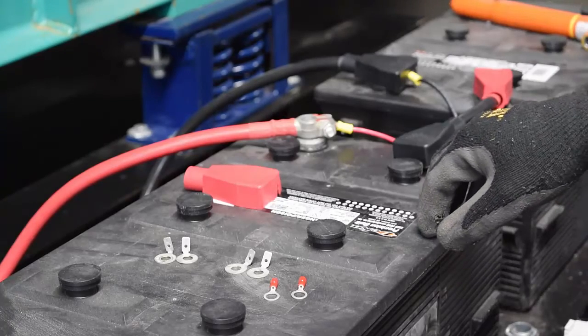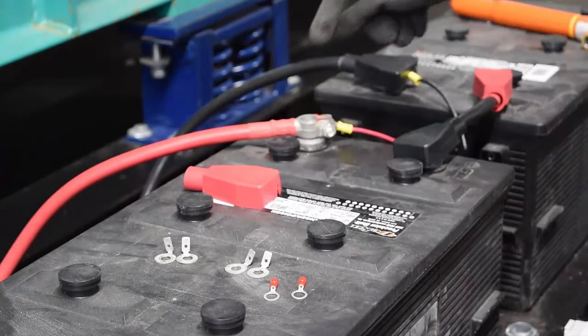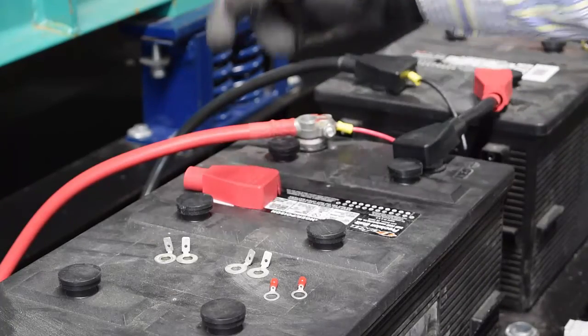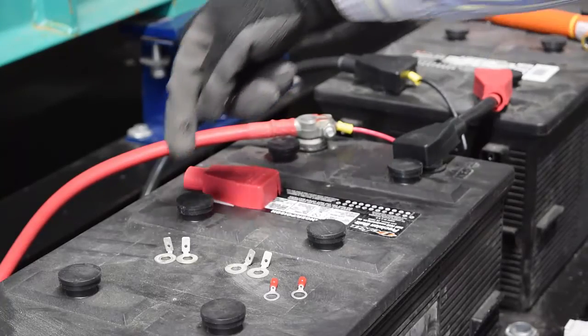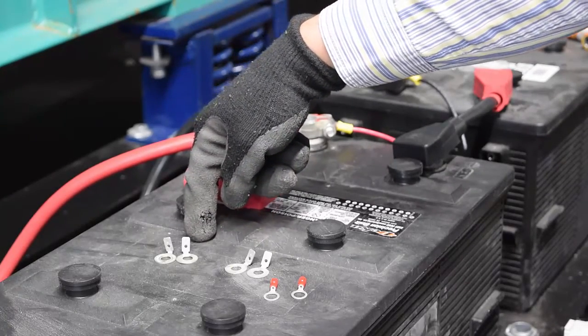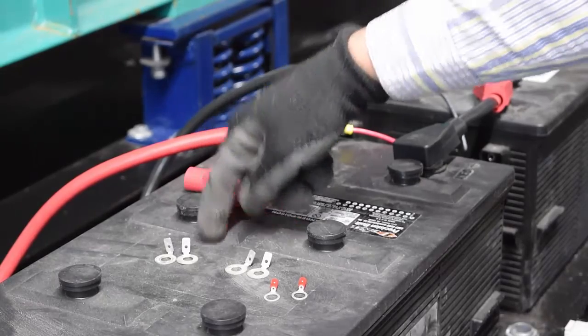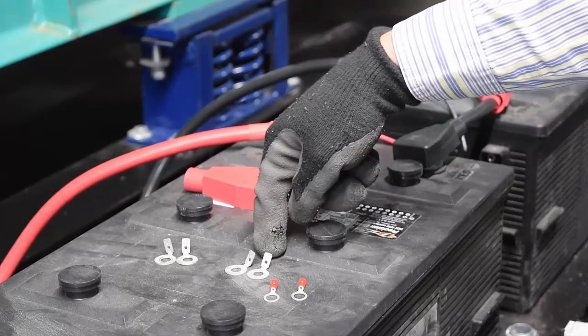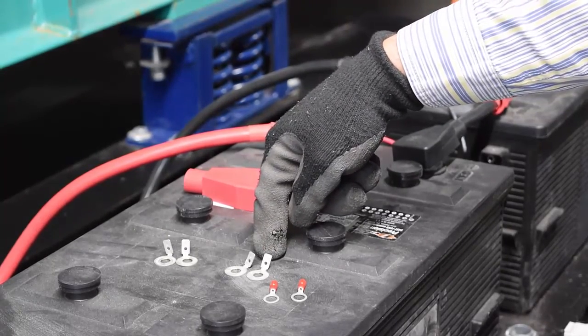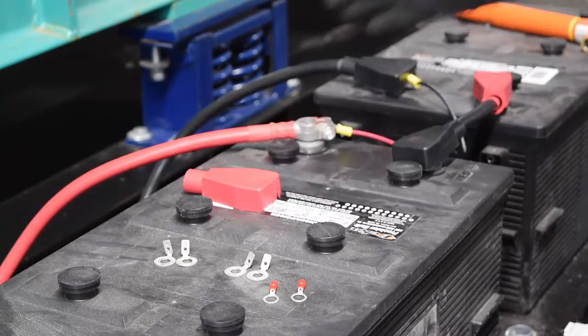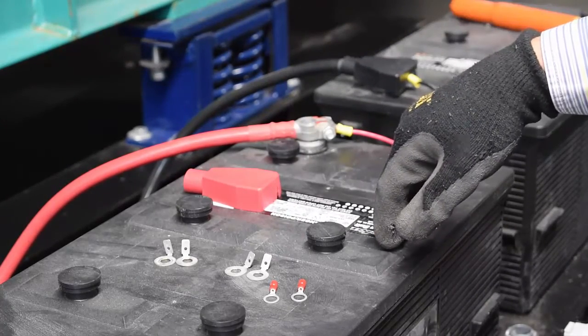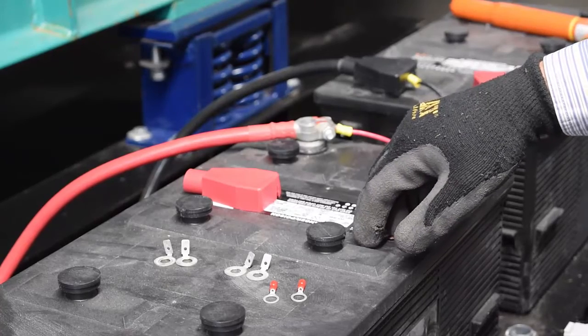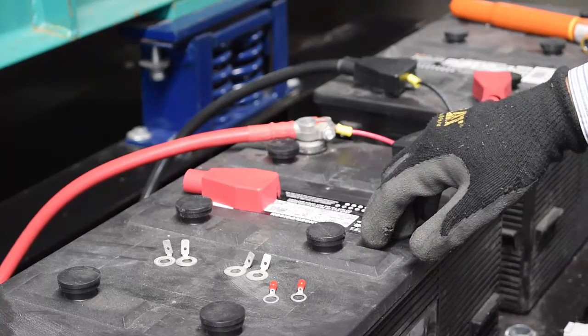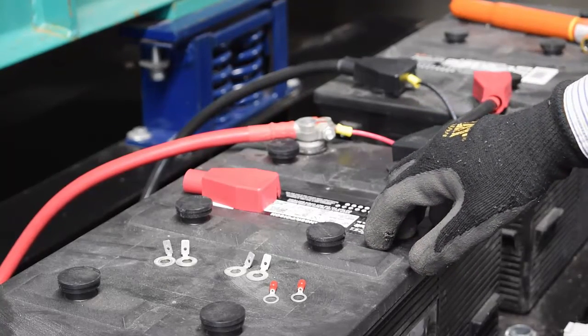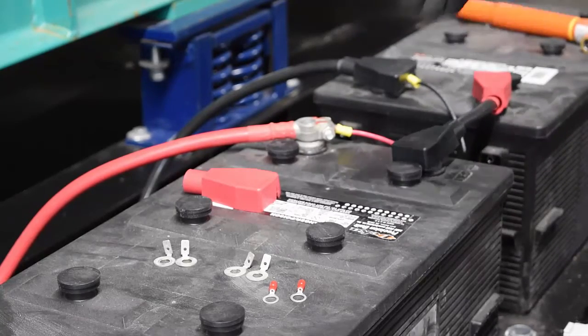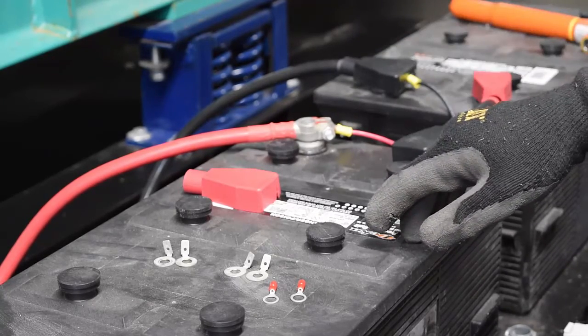Alright, we're ready to install the tab washers. Each battery post requires 2 tab washers. One set is to power the VTZ module and measure voltage, and another set senses impedance. If the string voltage is under 58 volts, then a BVI module will also measure the string voltage. Otherwise, the CellQ1 would measure string voltage by adding the individual unit voltages measured by the VTZs.